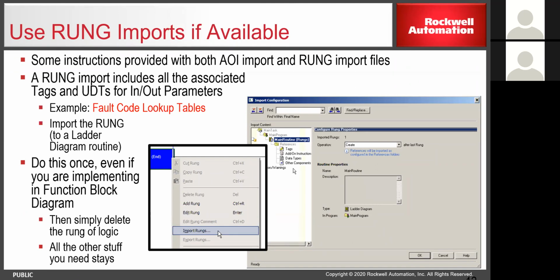So as part of those add-on instructions, they go through and say, well, what's the fault? Let's find a good fault. I think 111, which is a safety fault, out of phase, basically where one of the channels is faulted and you effectively have to power cycle the drive. It would go through the list and say, oh, I've got a fault 111 code coming from the drive. What is that? And it gives you the string information for that. It's already built for you, so you don't have to go look it up and make it yourself. So very, very useful.